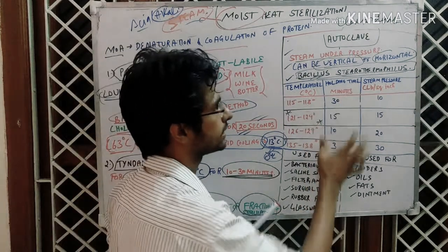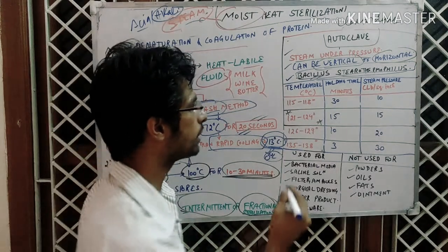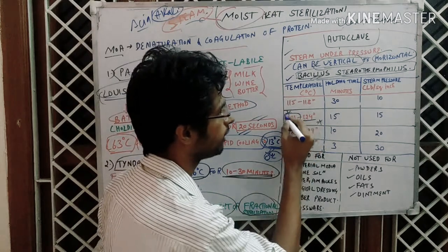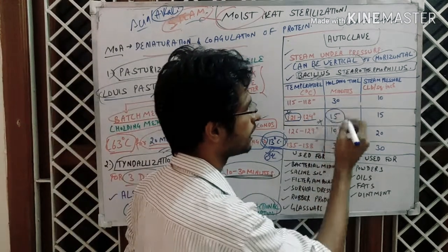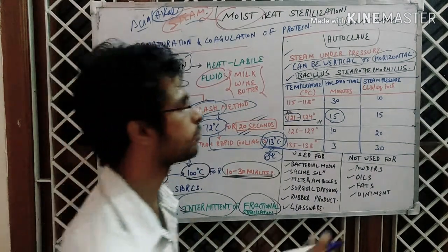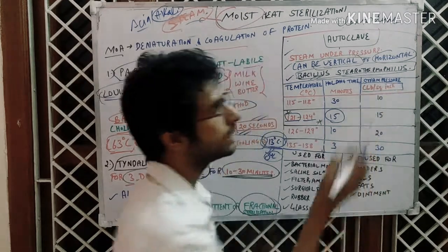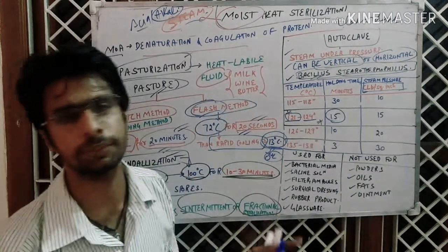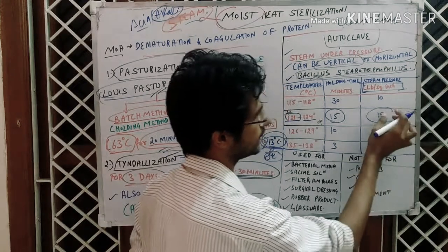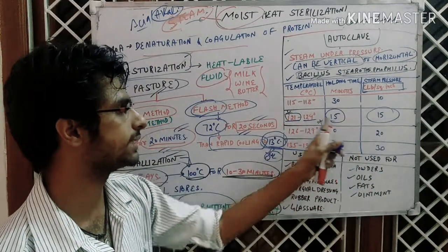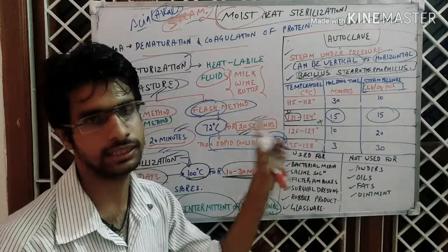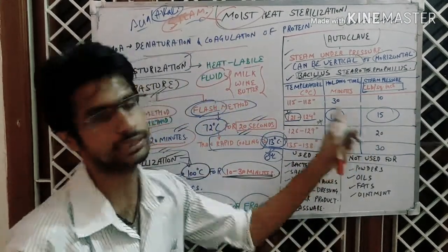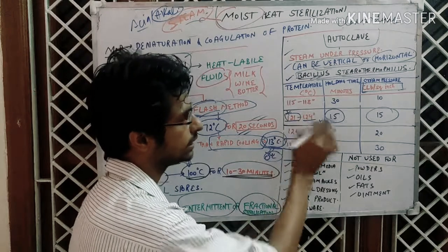There is a wide variety of temperatures that can be used in the autoclave, but the most common one is 121 to 124 degrees Celsius. In exam options you will get: 121 degrees Celsius for 15 minutes, with steam pressure as an important parameter. The unit is lb per square inch — lb stands for pound. At 15 lb per square inch pressure, 121 degrees Celsius for 15 minutes is the most common condition.